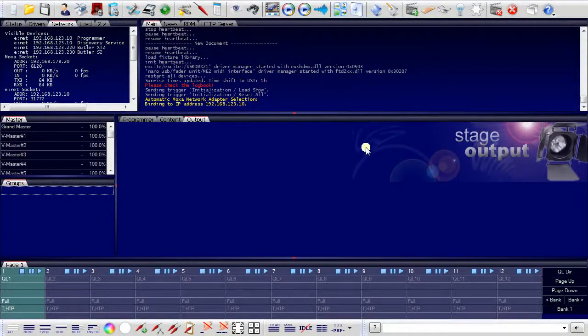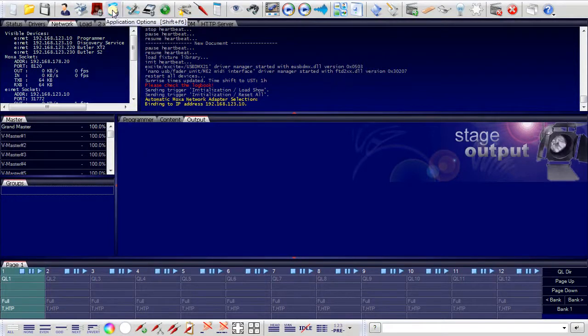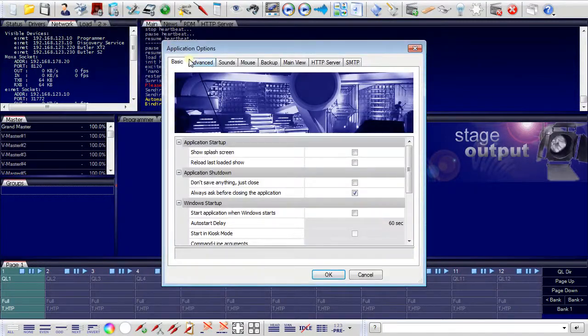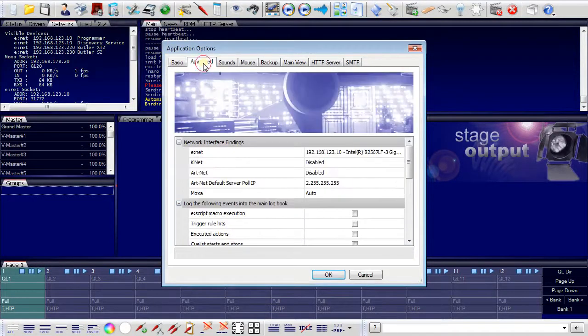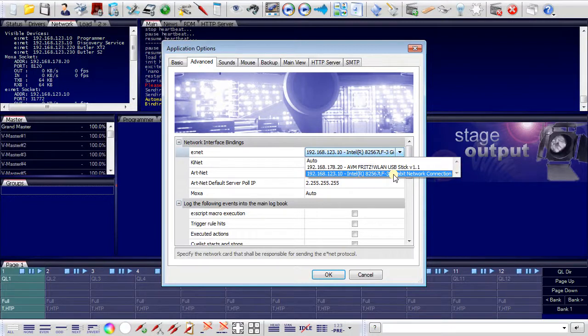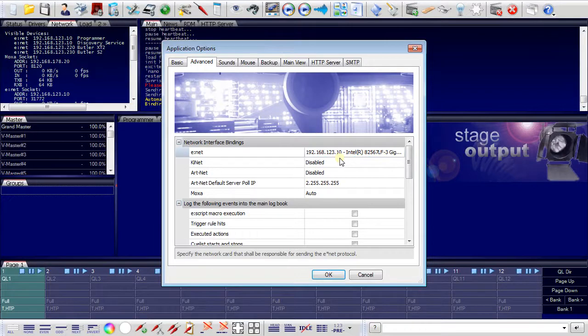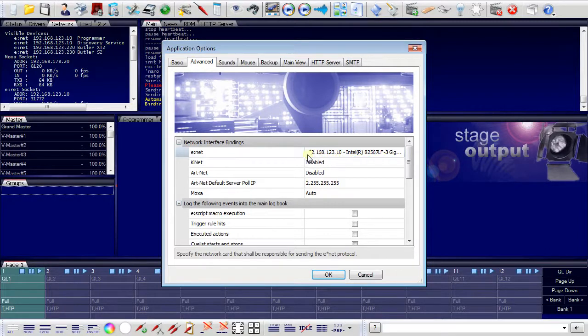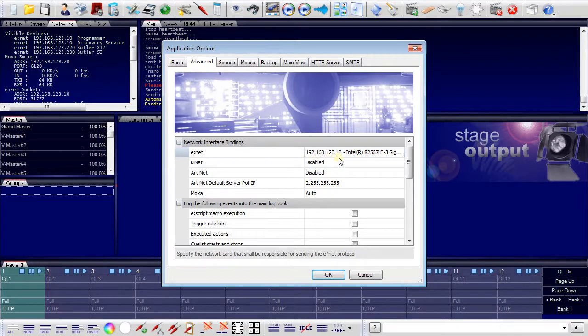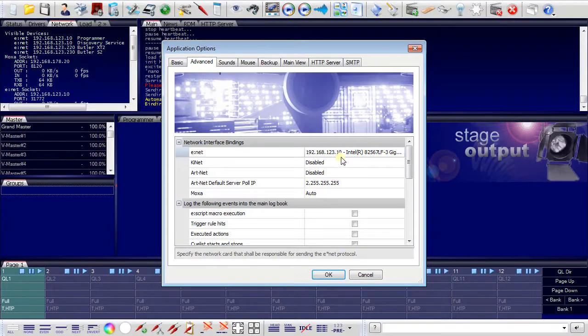The first step would be to set up the programmer correctly regarding the Ethernet interface we're using for connection to the engines. This is done via the Application Options in the Advanced tab. Here we have all possible Ethernet interfaces, and I use the local area network connection on the baseboard. Do not use extension 1 for the server because 1 is reserved for engines from the factory. They have a default Ethernet address of 192.168.123.1, and using 1 as a server address would result in an address conflict. In this case, I use 10, which is a safe address for the server.